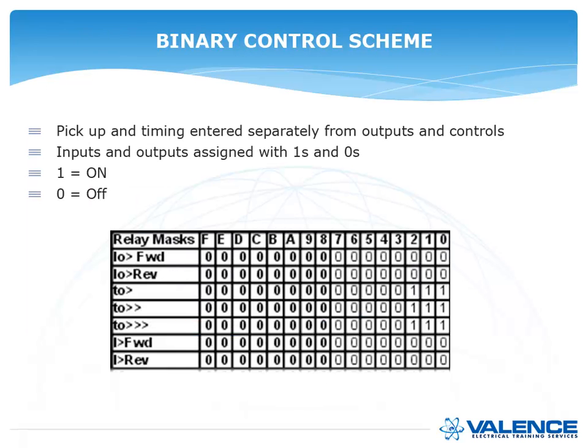A binary control scheme basically has a little chart with 0s and 1s. So the pickup and timing is entered in a completely different box from the outputs and controls. And then the inputs and outputs are assigned with 1s and 0s, where 1 equals on and 0 equals off.